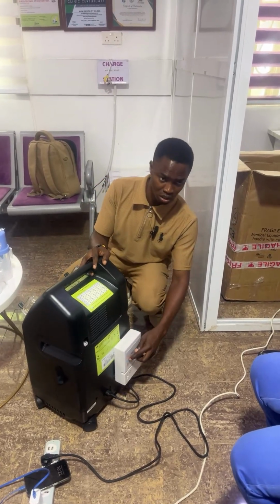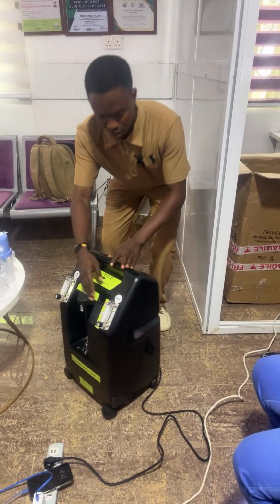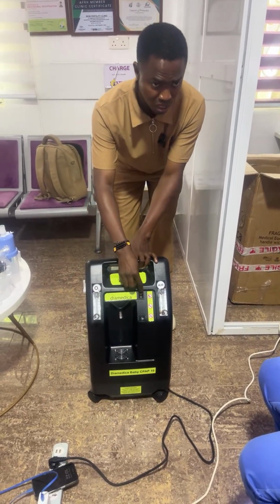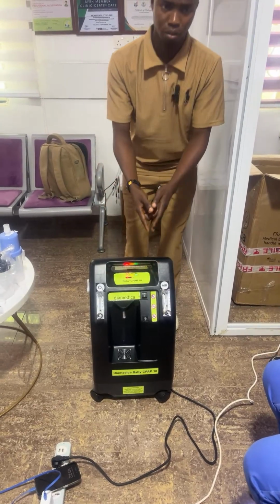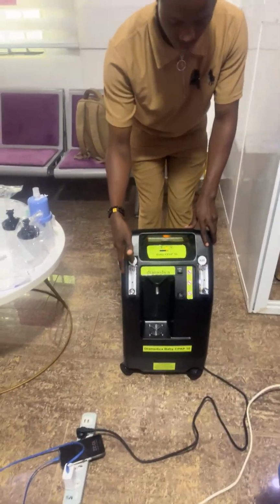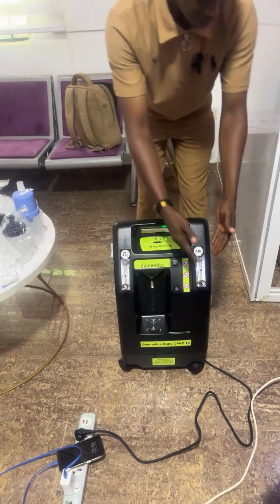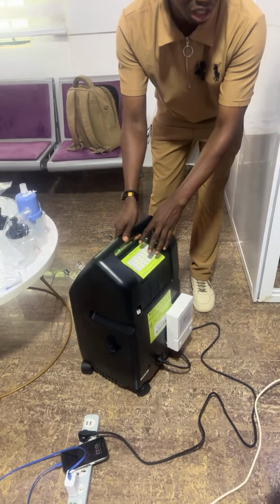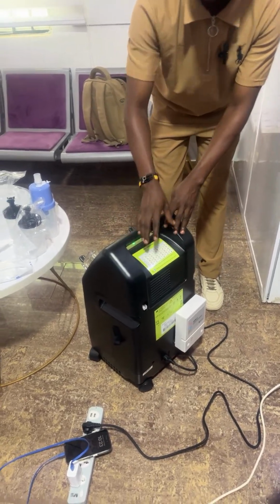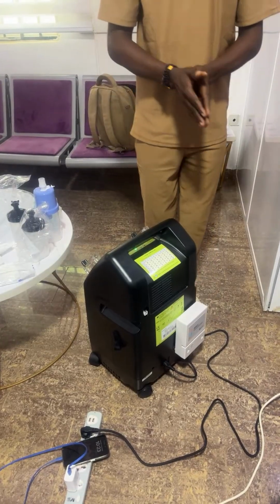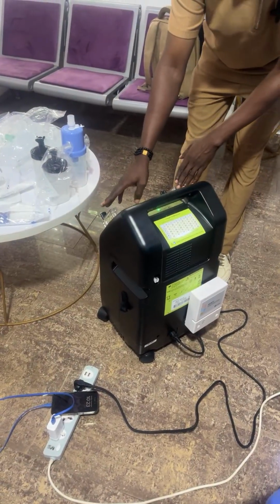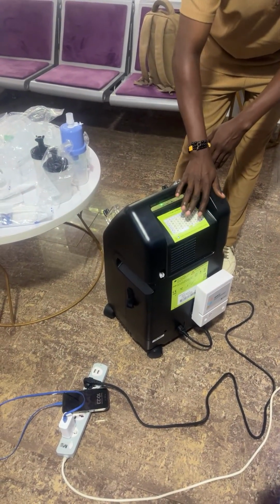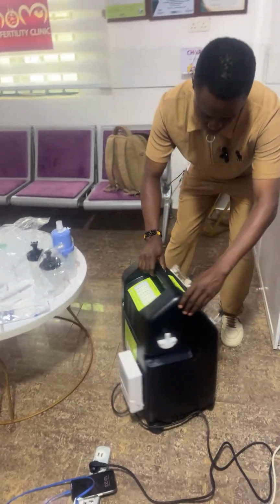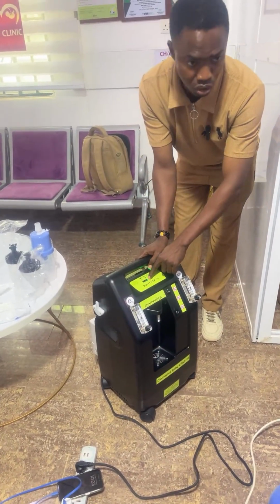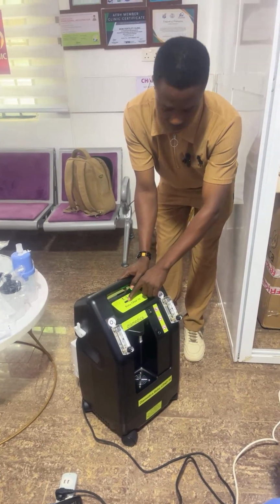It's not very bright, but it's turned green here. Then this is the power switch where you put on the machine. One is on, zero is off. You put it on. So this is the oxygen, you can see the O2 dial and the air dial. This is the mixing chart. One of the features of CPAP is that you are blending oxygen and not giving 100% oxygen. So these charts will guide you on what flow rates to set to achieve a particular FiO2. This is the chart here. Then this timer tells you the duration of use of the machine. I don't really need that.